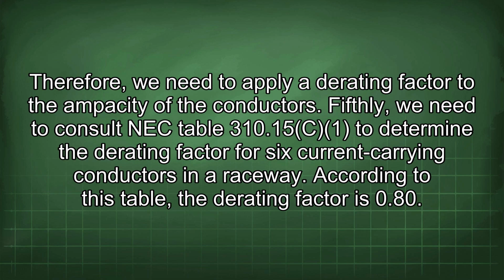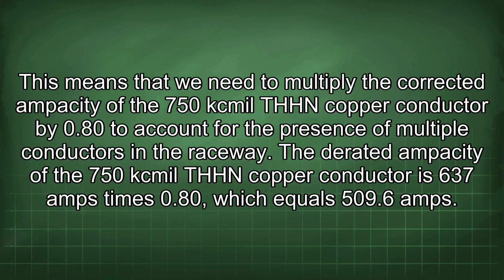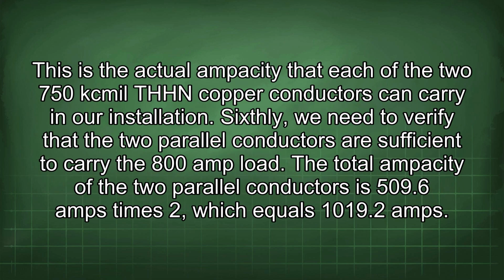Fifthly, we need to consult NEC Table 310.15(B)(3)(a) to determine the derating factor for 6 current carrying conductors in a raceway. According to this table, the derating factor is 0.80. This means that we need to multiply the corrected ampacity of the 750 kcmil THHN copper conductor by 0.80 to account for the presence of multiple conductors in the raceway. The derated ampacity of the 750 kcmil THHN copper conductor is 637 amps times 0.80, which equals 509.6 amps. This is the actual ampacity that each of the two 750 kcmil THHN copper conductors can carry in our installation.